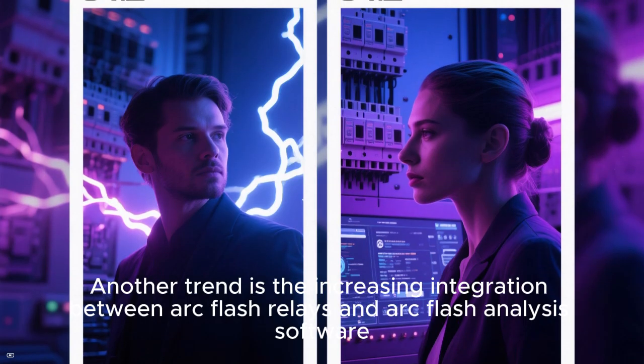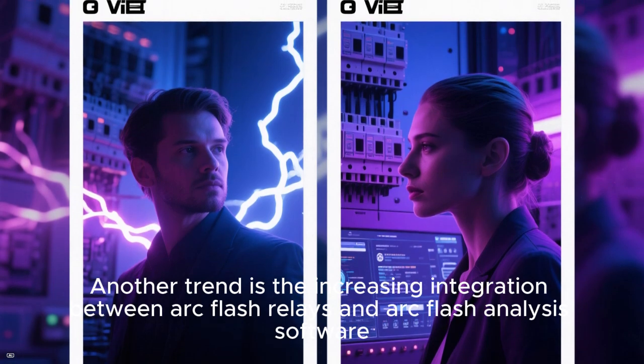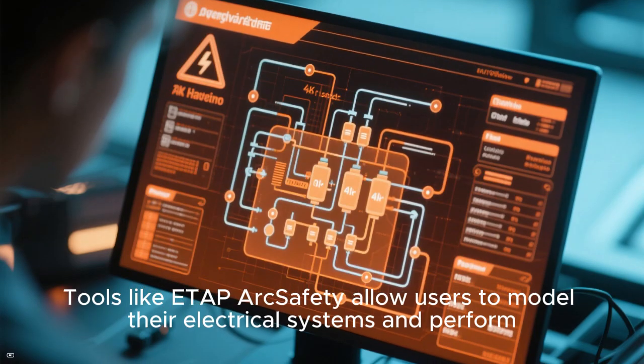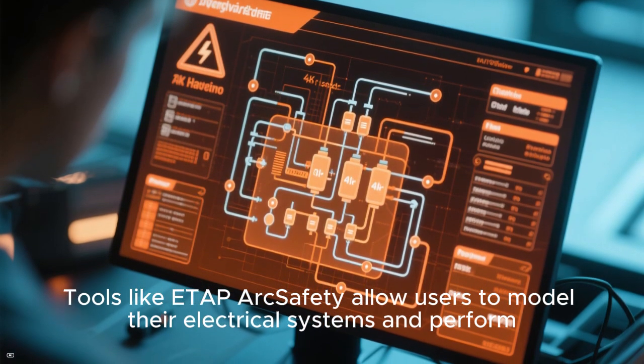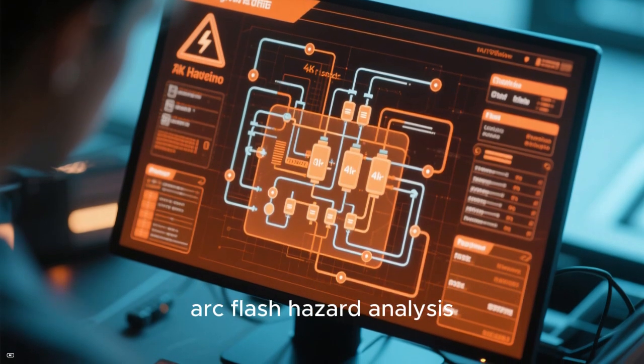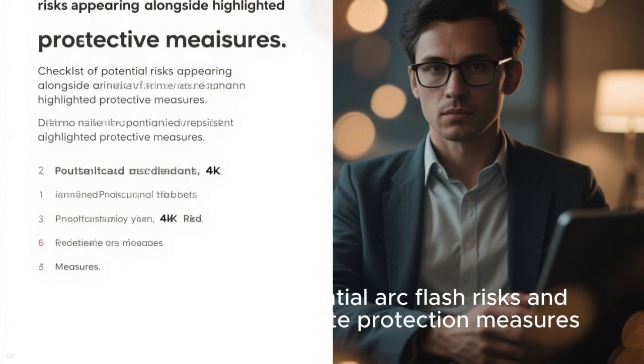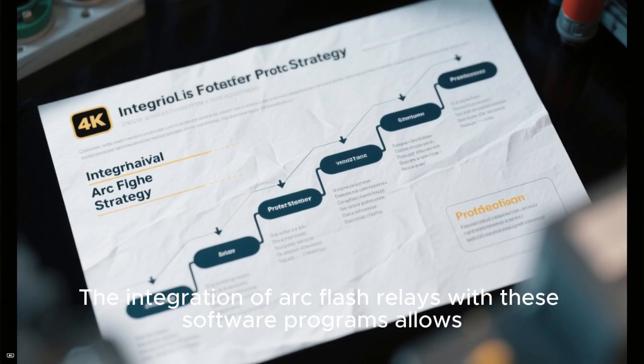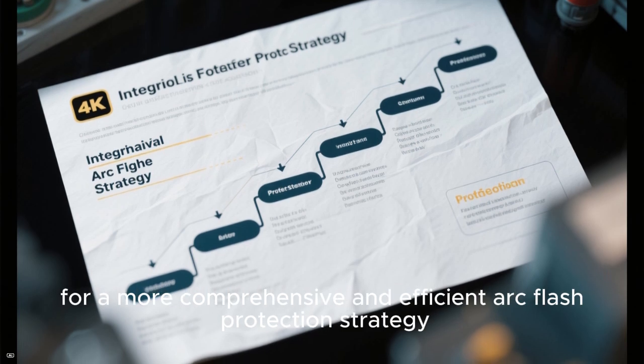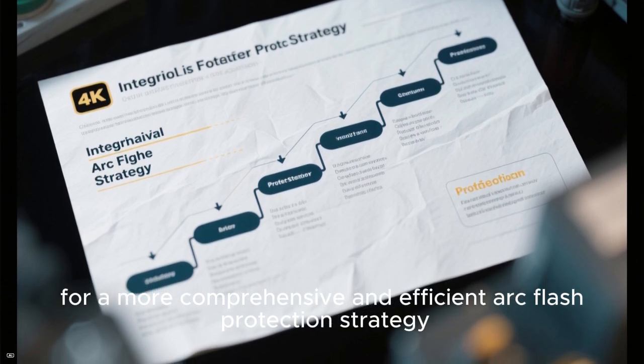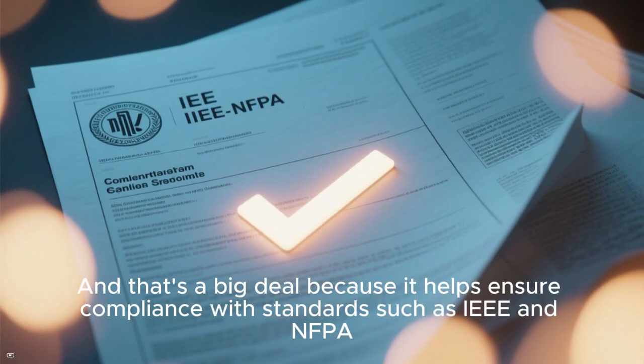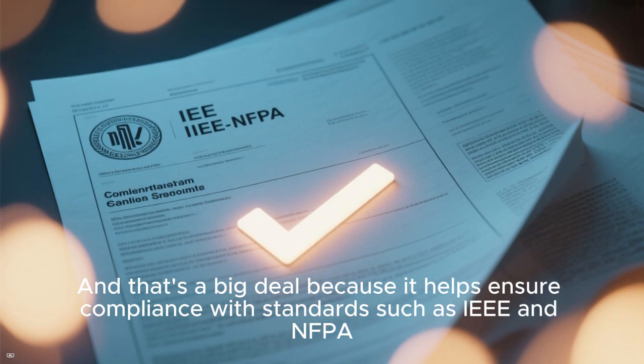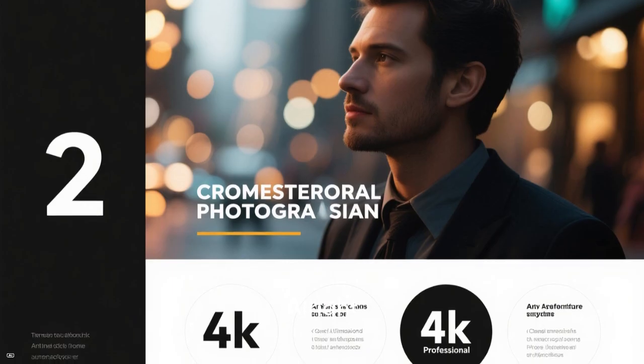Another trend is the increasing integration between arc flash relays and arc flash analysis software. Tools like ETAP ArcSafety allow users to model their electrical systems and perform arc flash hazard analysis. This helps identify potential arc flash risks and determine the appropriate protection measures. The integration of arc flash relays with these software programs allows for a more comprehensive and efficient arc flash protection strategy. And that's a big deal because it helps ensure compliance with standards such as IEEE and NFPA. Alright, so let's summarize what we've covered.